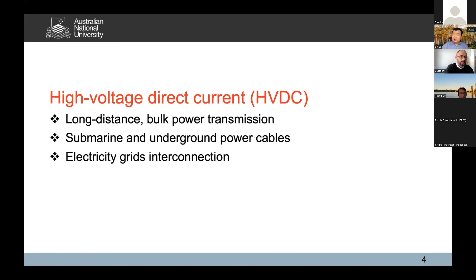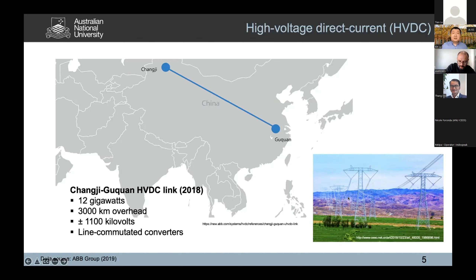Example: the Changji to Guquan HVDC link in China, operating since 2018, is the world's most powerful transmission line. It can transfer 12 gigawatts of electric power over a distance of 3,000 kilometers at 1,100 kilovolts. Transmission loss is relatively low, about 3% per 1,000 kilometers, so about 10% in total for this line. Here you can see the towers and overhead transmission lines.